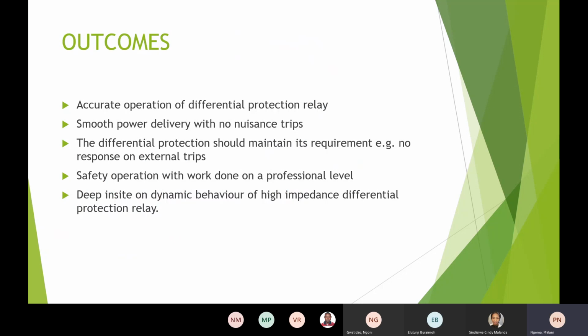The outcome is that at the end the project will be implemented. Tronox expects to see accurate operation, not the misoperation that keeps on happening in their plant, because now they are facing the problem where the relay is just not restrained from the external fault. The transformer is one of the major pieces of equipment delivering power into the plant and also the furnaces that they have. If one relay picks up the fault, whether it is internal or external, it just operates.